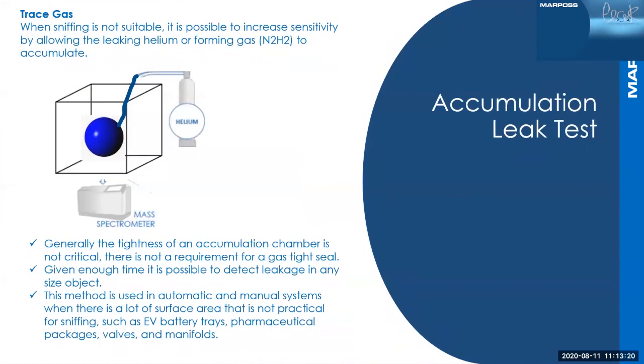When the parts really start getting bigger, one of the things we're starting to see used a lot more often is what we refer to as an accumulation leak test method. Basically, we put the part into a chamber. It doesn't need to be as special or critical as the vacuum chambers, but we pressurize the inside of the part, look for a leak, and let the helium accumulate on the outside of the part. This is usually for larger leak rates. You'll see this used in batteries, cylinder blocks, cylinder heads, things along those lines where the leak rates aren't as tight that you need the hard vac systems for.